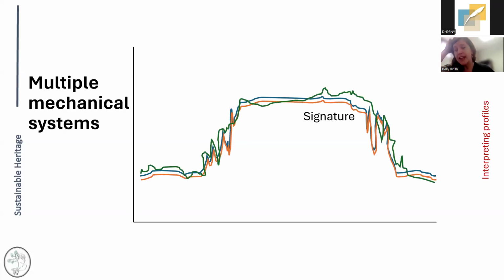So this isn't exactly a profile, but I wanted to show you, if you pull up data from multiple spaces across your institution and you're looking at dew point across a variety of spaces, one of the other things you can do is look for a dew point signature. If we were all to draw a picture of a cat, we'd probably all come up with some version of a cat, but it wouldn't look all the same. So each air handler, even though they're all reaching relatively similar set points, is going to go about it in slightly different ways, and it gives what's called a dew point signature.